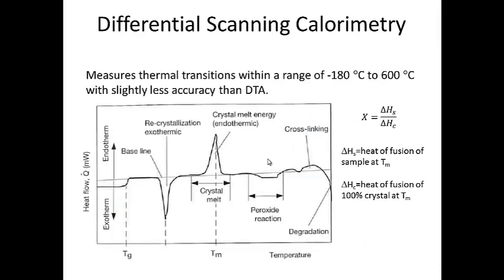Differential scanning calorimetry is a technique we've already talked about and it's a technique that's typically used to measure thermal transitions within a range of approximately minus 180 degrees Celsius or liquid nitrogen temperatures up to 600 degrees Celsius, and it's slightly less accurate than differential thermal analysis.